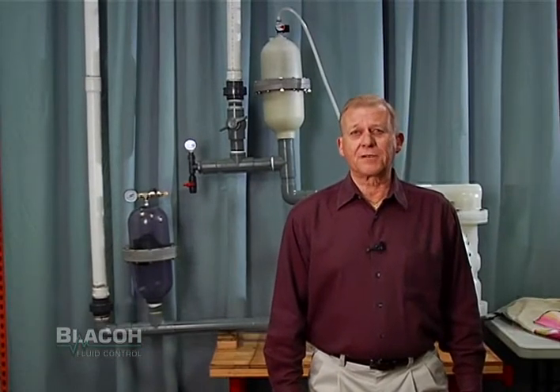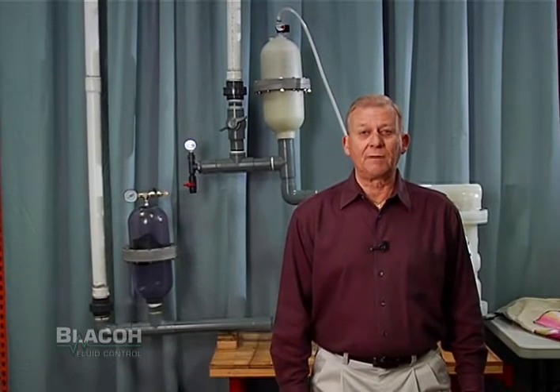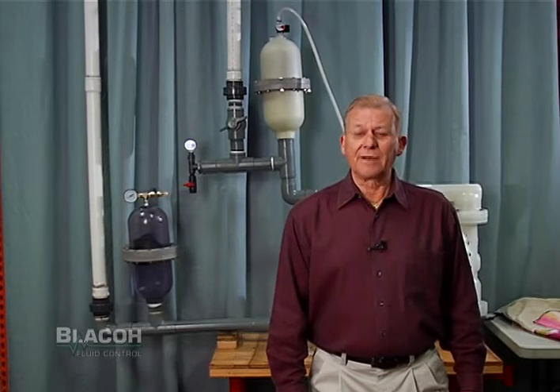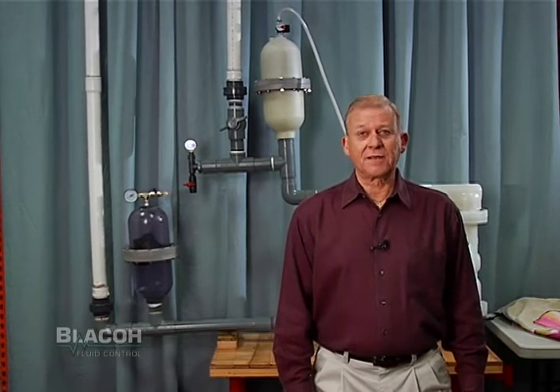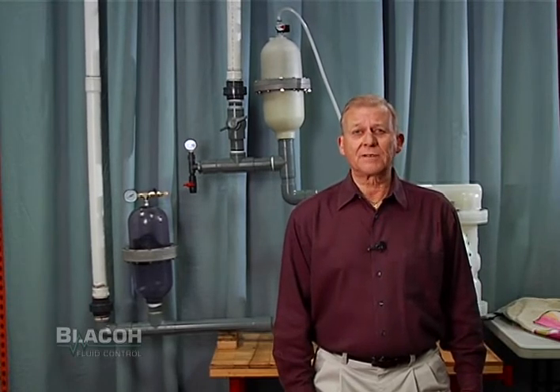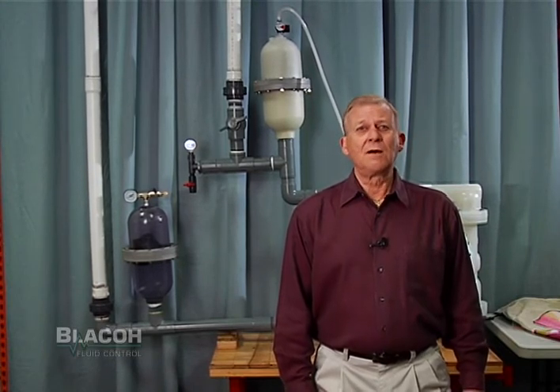We hope that this demonstration has shown that with the use of a discharge dampener on the discharge pump and the inlet stabilizer on the inlet side, we can protect the pump, the piping, and system components. We know that adding a pulsation dampener and an inlet stabilizer will extend the life of your liquid handling systems components and, most importantly, protect your system, allowing you to pump and transfer more products for a longer period of time between maintenance and repairs.